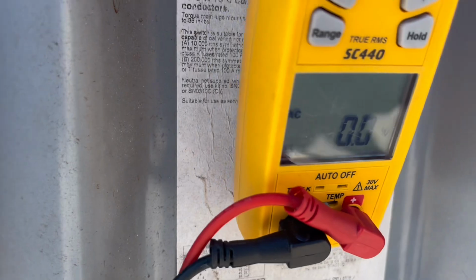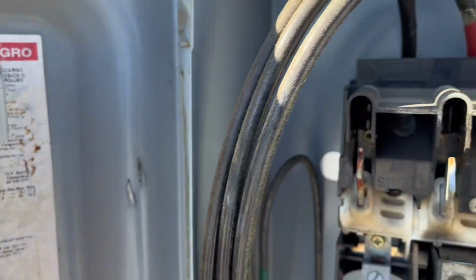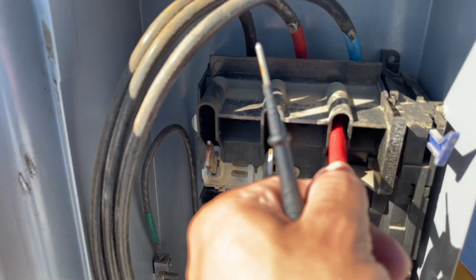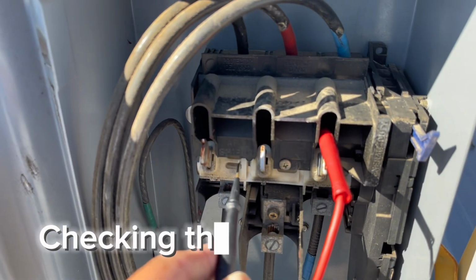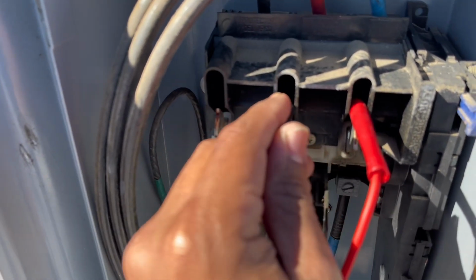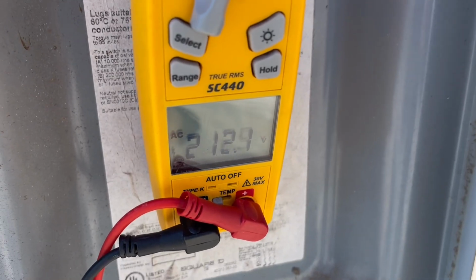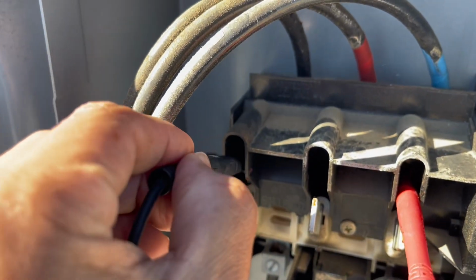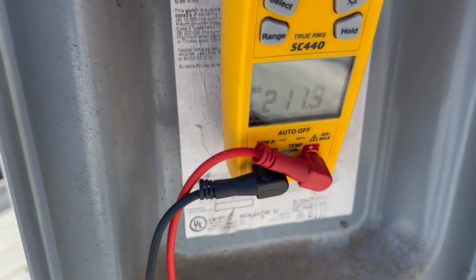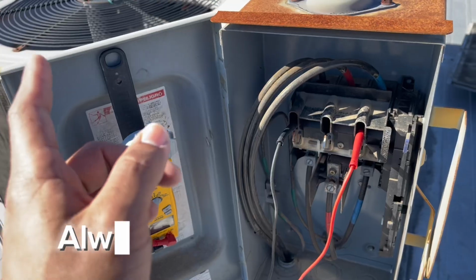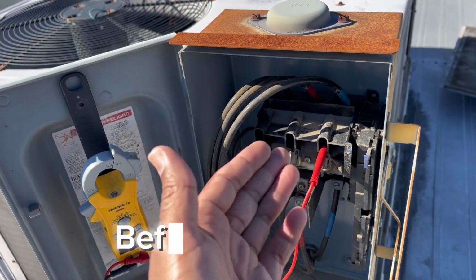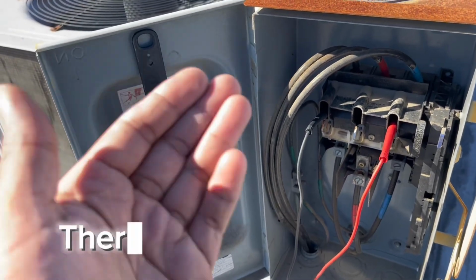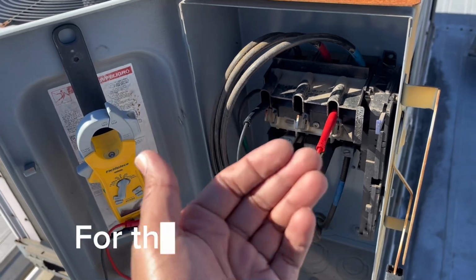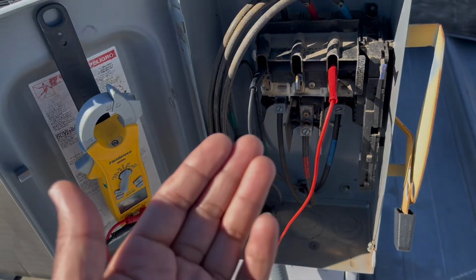Alright, so after turning the breaker back on, we are going to check the voltage and see what kind of voltage we have, in case we have any. Okay, so check again. Yeah, we definitely have some voltage now at the base. Yep, perfect. Now, before we turn this power on again, I would like to check the compressor, because sometimes this issue happens because the compressor starts failing and can cause the breaker to trip. So let's see how that compressor looks.